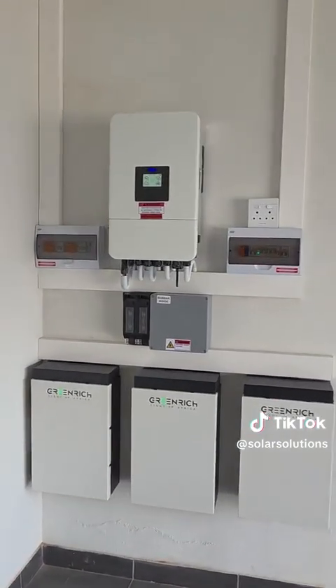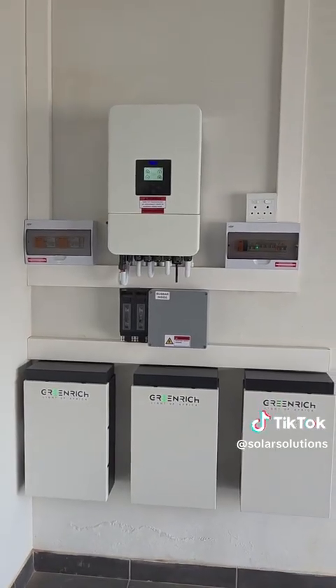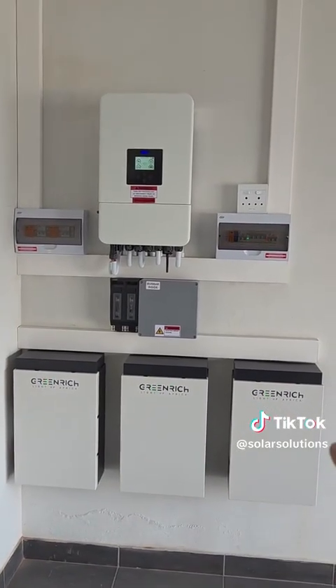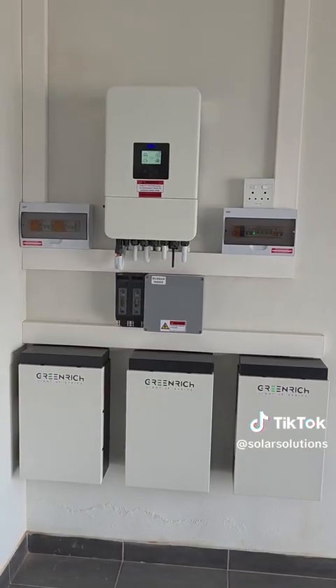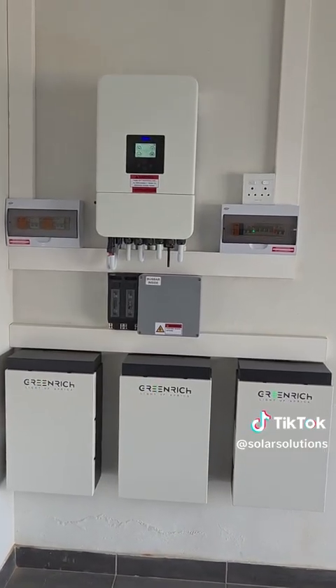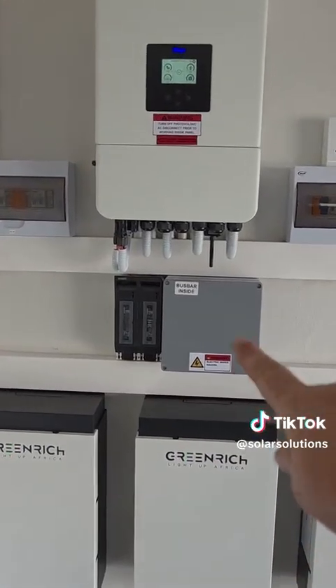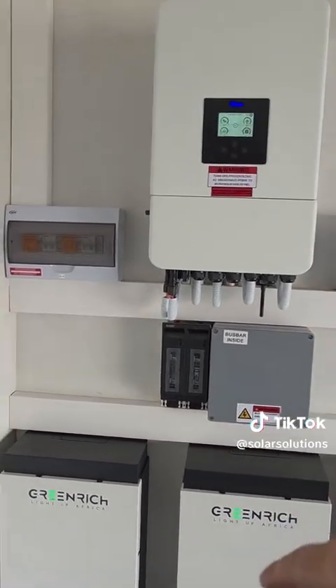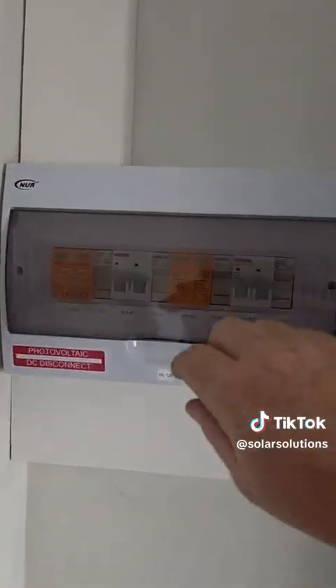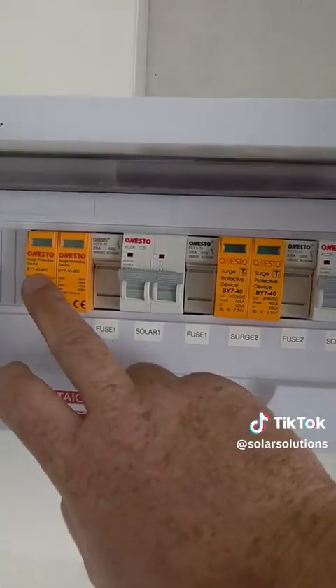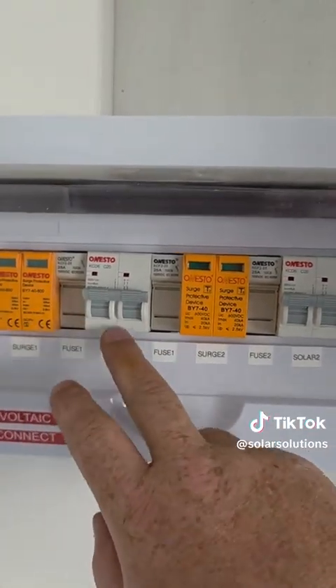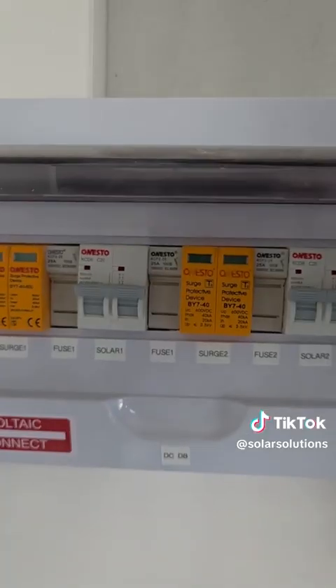So we've got an 8 kilowatt Deye inverter with 3 5 kilowatt Greenrich batteries. As you can see, the lights are flashing at the moment, so we're just giving it a nice boost charge to get it full for the first charge. And then we've got the bus bar, and then it goes through the battery disconnect into the inverter. On this side, we've got our DC combiner box with 2 strings. So we've got our surge protection, 2 fuses, and a solar DC breaker for the 1 string, and then the same for the 2nd string.